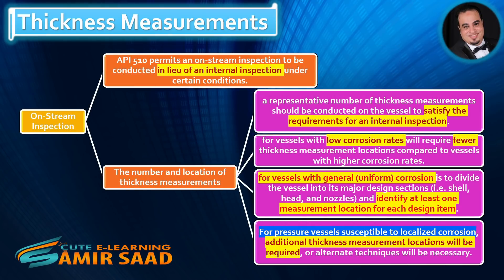On-stream inspection: API 510 permits an on-stream inspection to be conducted in lieu of an internal inspection under certain conditions. A representative number of thickness measurements should be conducted on the vessel to satisfy the requirements for an internal inspection.